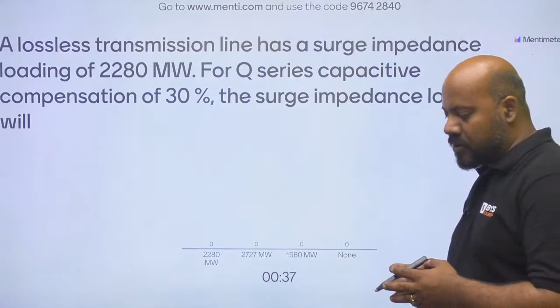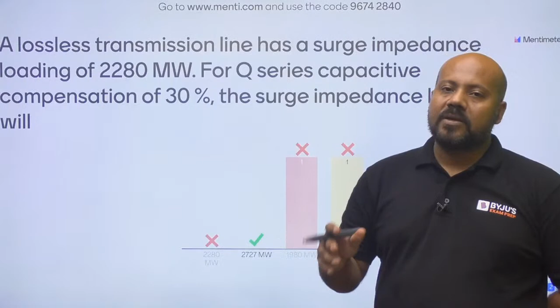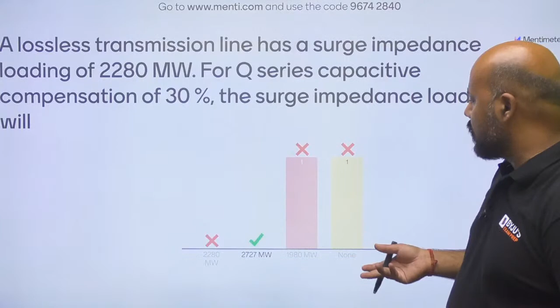First thing you have to understand is how you are relating the surge impedance loading with the surge impedance. What the series capacitive compensation is going to do is compensate some of the line reactance, series line reactance. How much? He is saying 30%. So what is the remaining one? The remaining one is 70%. So in the second case, you have to choose the line reactance not as X or L, but as 0.7X. That is the only thing you have to do, and relate the surge impedance loading for the two cases.